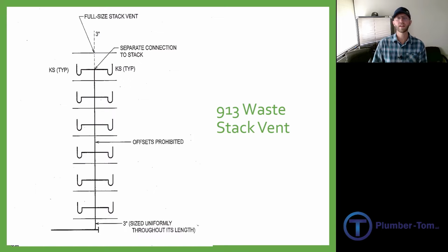We now have 12 fixtures as a maximum for this particular 3-inch stack that can be connected in, all these kitchen sinks. Now obviously this only works if you have the identical layout or fixtures stacked right on top of each other from one floor to the next. But when that is the case, if you can run a pipe completely vertical up through all of that, you can catch quite a few fixtures.